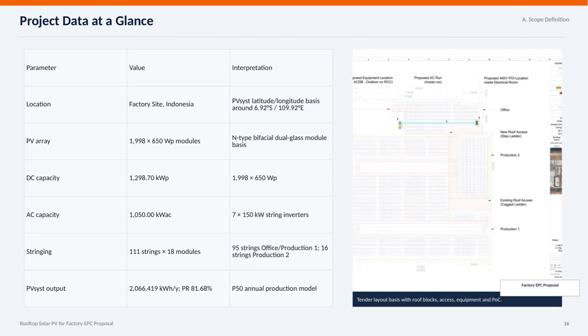Here we have the key project data at a glance for our rooftop solar PV proposal for the factory EPC. The scope focuses on installing a large PV array consisting of 1,998 modules, each rated at 650 watts, making for a total DC capacity of nearly 1,300 kilowatts. These are N-type bifacial dual-glass modules, chosen for their efficiency and durability. On the AC side, the system uses 7 string inverters, each rated at 150 kilowatts, delivering a combined capacity of 1,050 kilowatts. The array is organized into 111 strings with 18 modules each, distributed mostly across the offices and production areas.